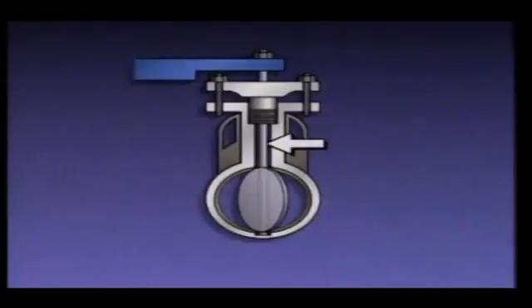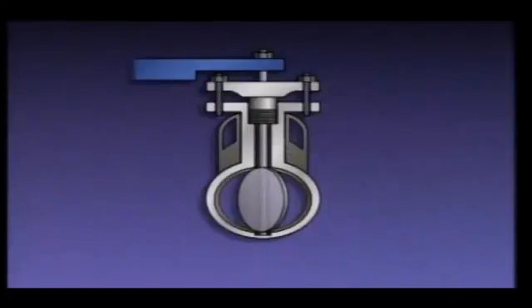The disc is attached to the stem, which is used to rotate the disc when the handle is moved. The flow rate through the valve is adjusted by changing the angle of the disc. The butterfly valve requires only a 90-degree or one-quarter turn of its handle to go from fully open to fully closed. When the handle is in line with the valve's inlet and outlet, the valve is fully open; when the handle is perpendicular to the piping, the valve is fully closed.